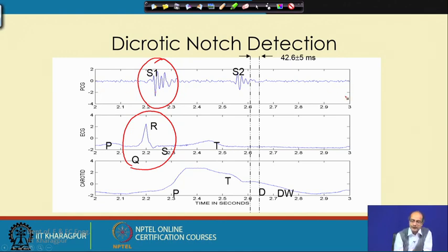The PCG signal we are getting here is a very clean rendering of it. Actually, it is superimposed with lots of noise, including power frequency noise and high frequency noise. So, we do not get such a clean signal. We need to have some idea of where the S1 and S2 sounds are occurring. The first trigger to get the position of S1 comes from the QRS complex, and already we have seen how we can capture the QRS complex, the three algorithms we have learned.